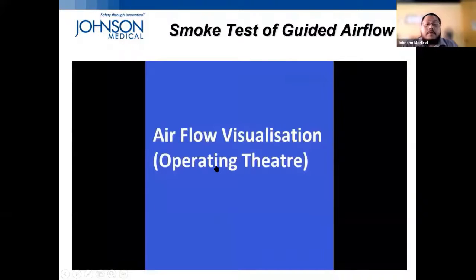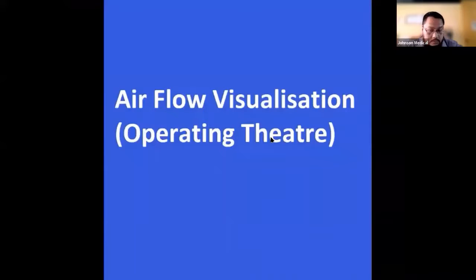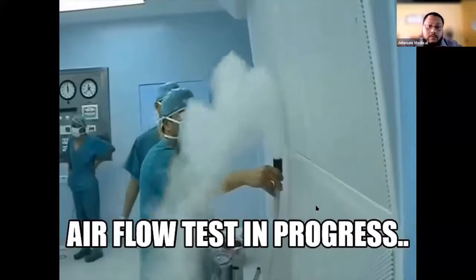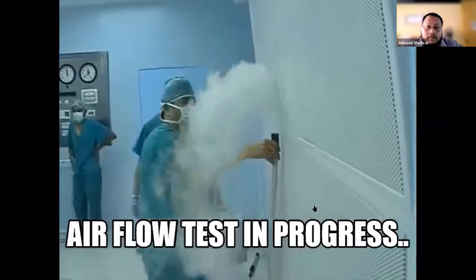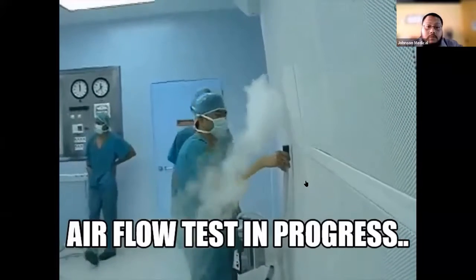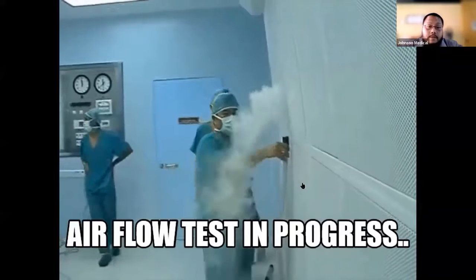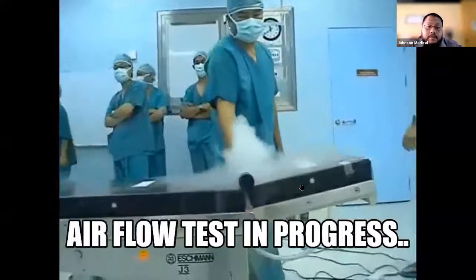Here we're going to show you a video of the airflow visualization test we did in an OT in Sabah. So you can see that the airflow coming from the guided airflow is very gentle.